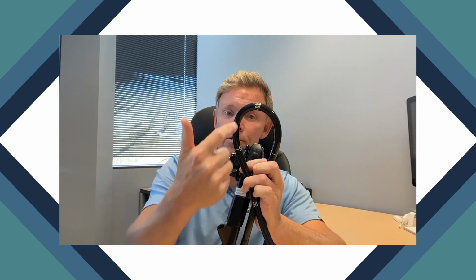There's an air channel. There's a water channel. There are wires in there. There are sometimes an auxiliary water channel in there. There are fiber bundles in there, glass fiber bundles that distribute the light from the light source back to the tip of the scope at the end of the insertion tube here. So there's a lot of components packed in this tube, and there's really not any extra space. So what that means is if you overcoil the scope, if you coil this too tightly, right now it looks like this tube can handle this, but keep in mind you're putting a lot of pressure on all those components inside this tube. They're going to wear out faster if you routinely do something like this, or they could be damaged from one event like this of overcoiling the scope.